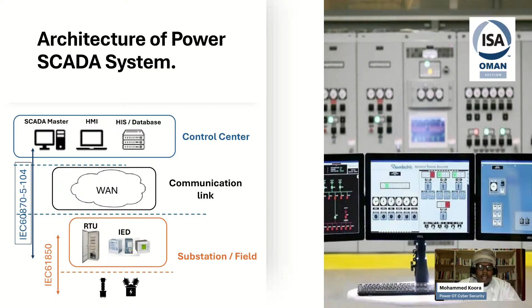In brief, I'll go through how communication works inside the substation. First, we have the inputs. In our power system, we have limited parameters taken from the site: current and voltage. The rest, like frequency, power factor, and real power, are calculated inside the relay.